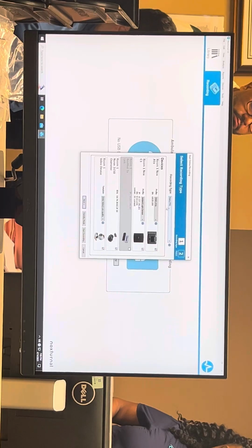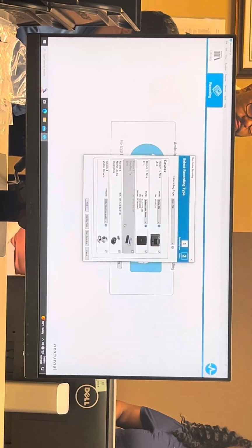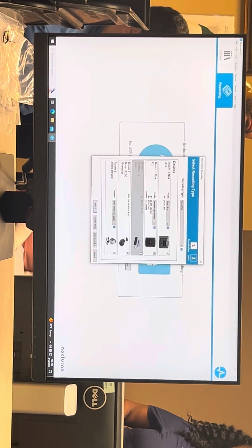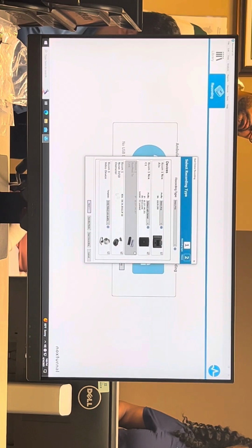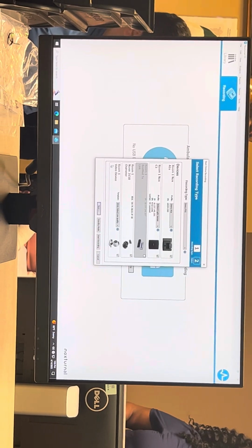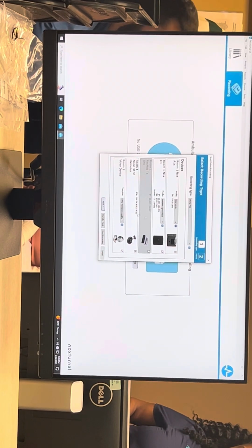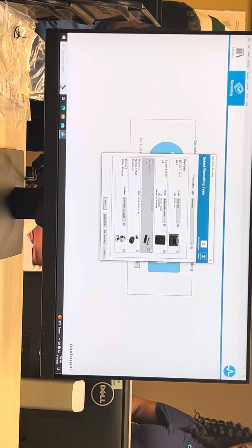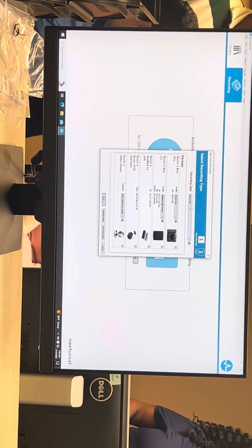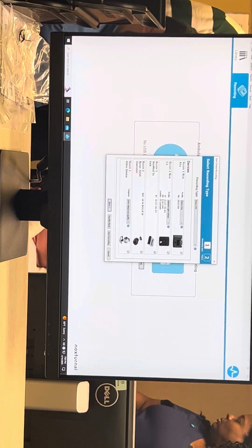And because this is a PSG recording type, you see how it's grayed out the TX link? Because it's not expecting to connect to that device. If you had a SenTec or some sort of ETCO2 device in this room, that would be listed here as well. And it either would be grayed in or it would be included if this was like a pediatric recording type or something along those lines.